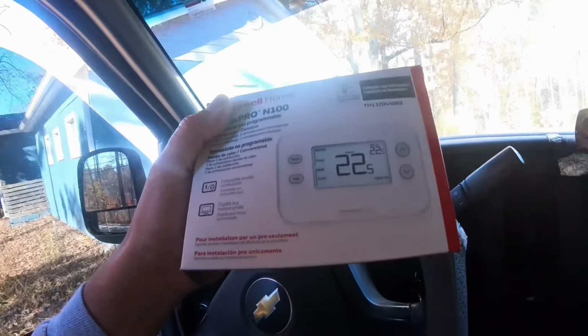A little background: I'm coming back to this crawl space job. I was out here last week and bypassed everything to just get them in heating mode with the heat pump temporarily. So I'm here now with a new thermostat, a new dual fuel thermostat, and a new sensor. This is the thermostat, and it is dual fuel compatible.